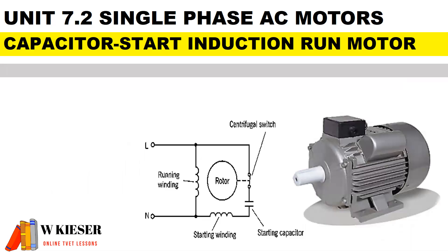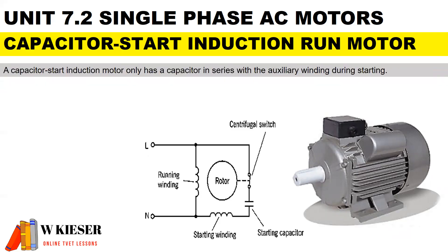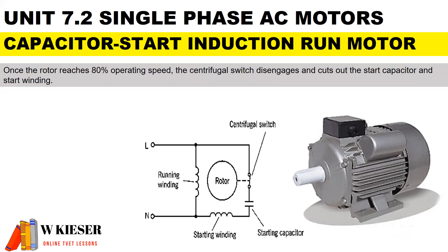Here we have the capacitor start induction run motor, and it's important to note that there is only one capacitor. It has higher torque, and its main application is swimming pool pumps, as an example. A capacitor start induction motor only has a capacitor in series with the auxiliary winding during starting. Once the rotor reaches 80% operating speed, the centrifugal switch disengages and cuts out the start capacitor and start winding.